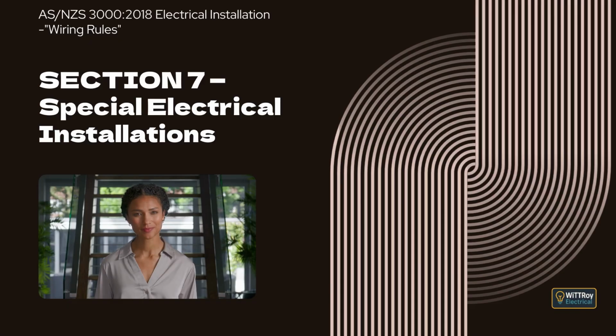Clause 7.3.1 General. This clause explains that electricity generation systems may take several forms. It explains that an alternative or supplementary supply may be provided by a generator set, typically driven by a combustion engine, which may supply an alternative or standby alternating current supply when the normal supply fails, may act as the primary power supply to an installation, or may be used as part of a standalone power system. It also explains that a standalone power system is not connected to a network provider's distribution system and may be supplied from sources such as photovoltaic arrays, wind turbines or mini hydro turbines, or engine-driven generator sets that provide either alternating current or direct current.